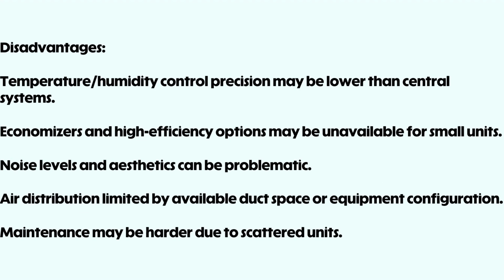However, decentralized systems also have trade-offs. Temperature and humidity control are less precise than central systems. Economizers or advanced energy recovery may not be available on smaller units. Air distribution design can be limited by fan capacity or space. Maintenance can become repetitive due to many distributed units. Aesthetics and noise can be concerns if equipment is exposed near occupied areas. Despite these limitations, decentralized systems remain a practical solution for many projects where cost, schedule, and flexibility matter most.